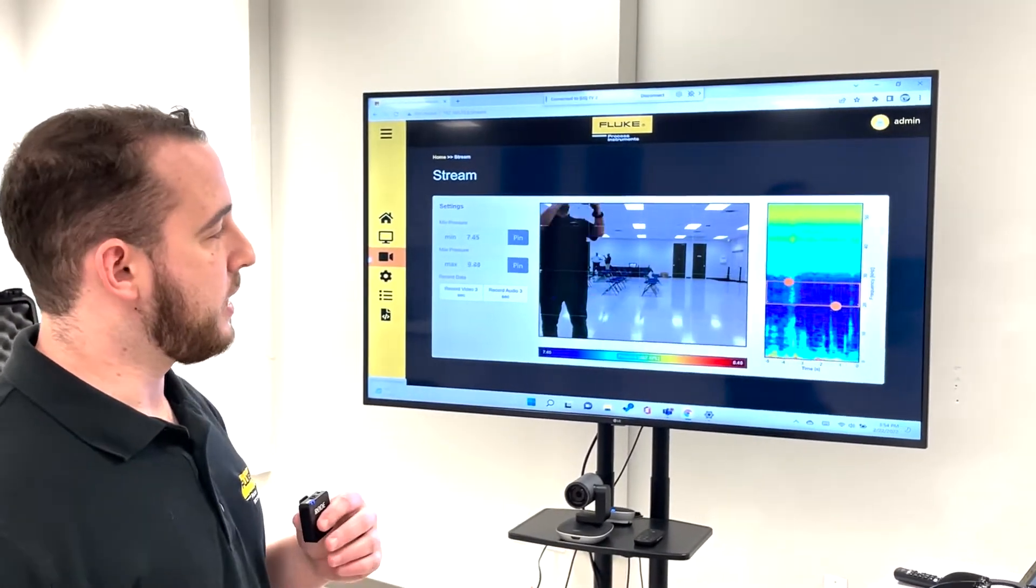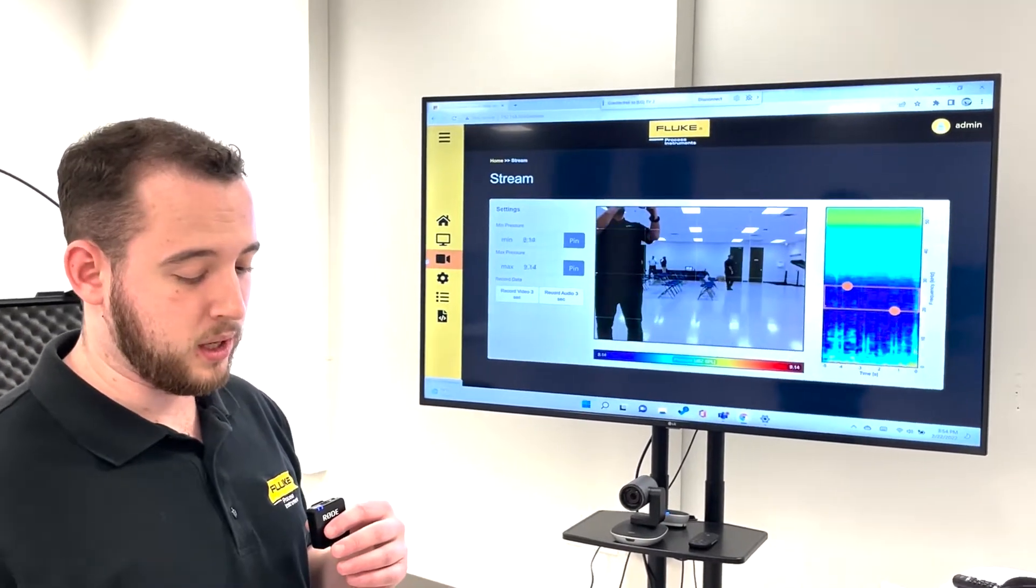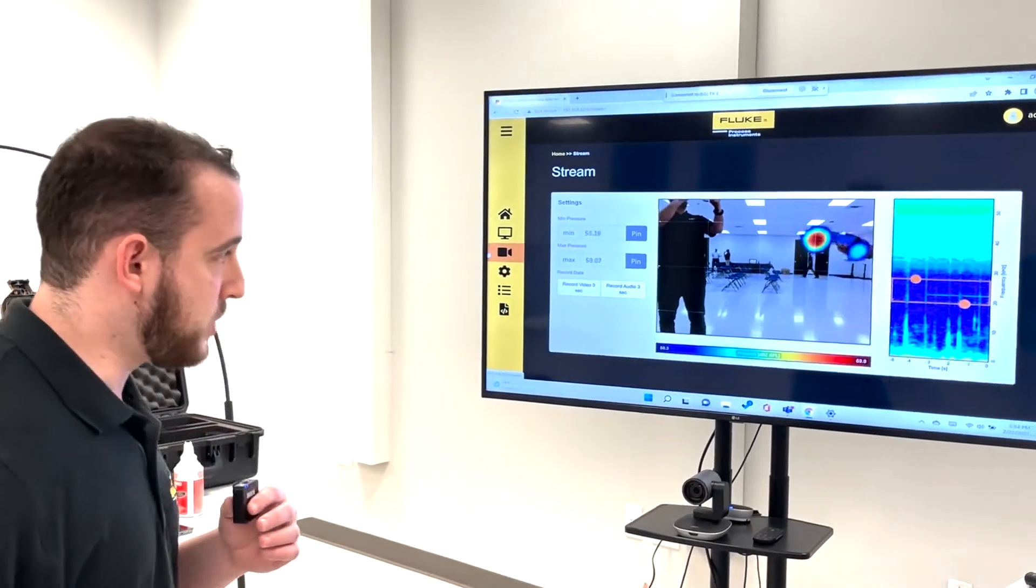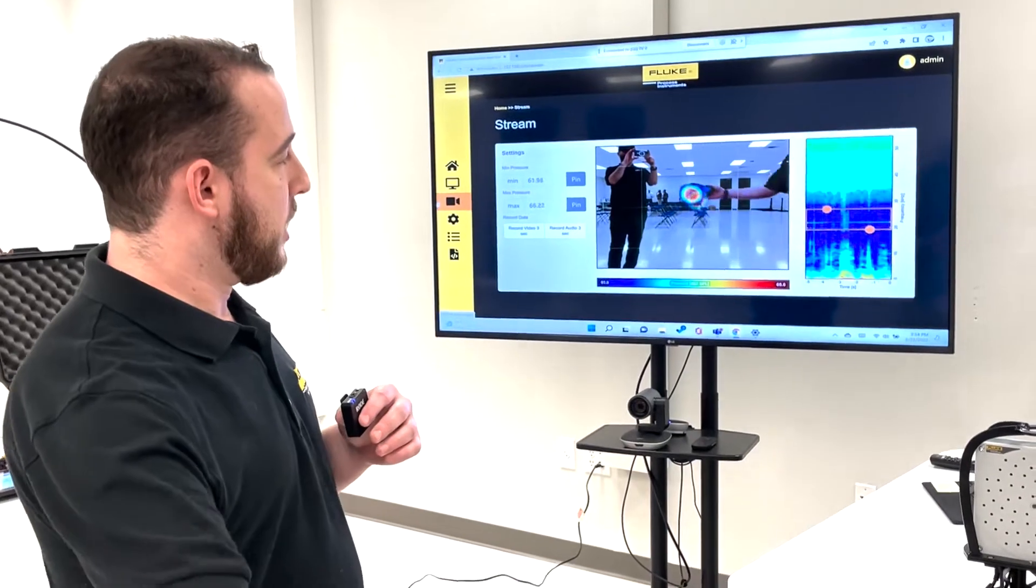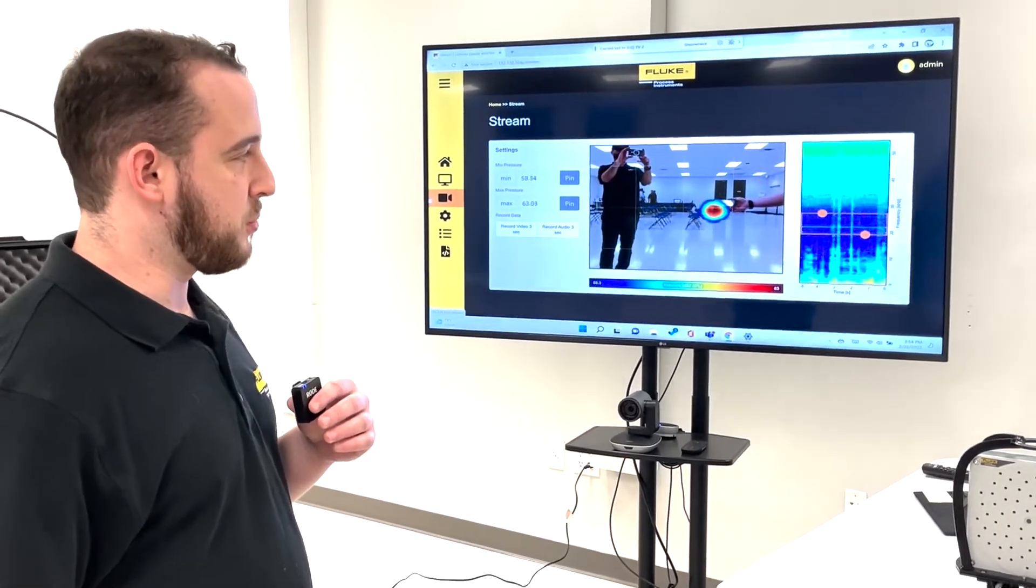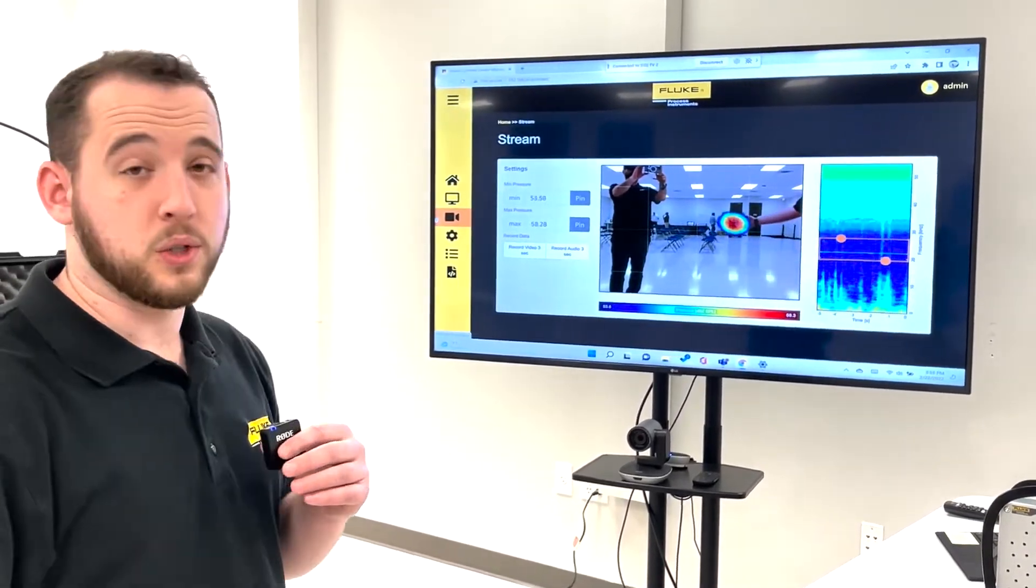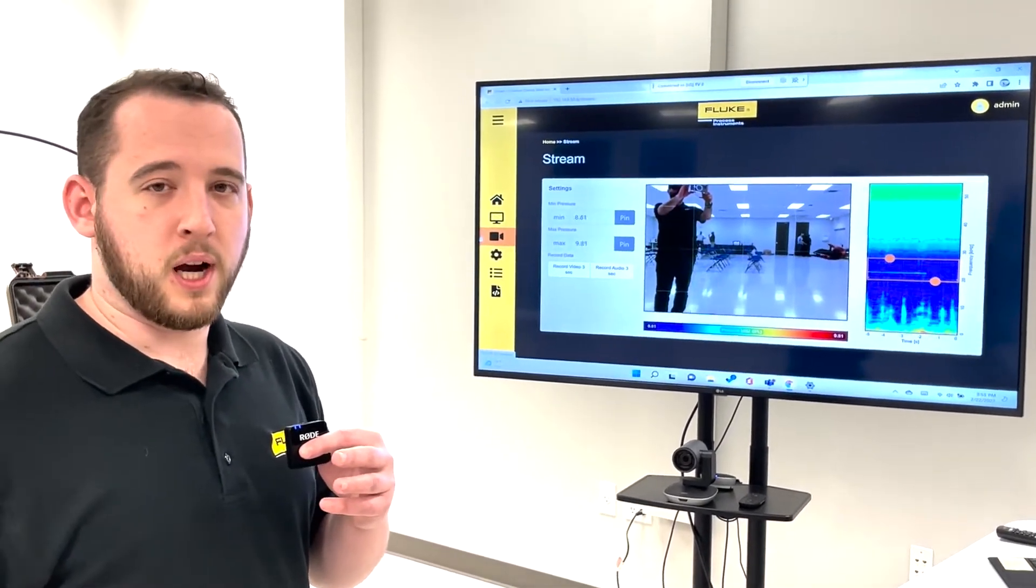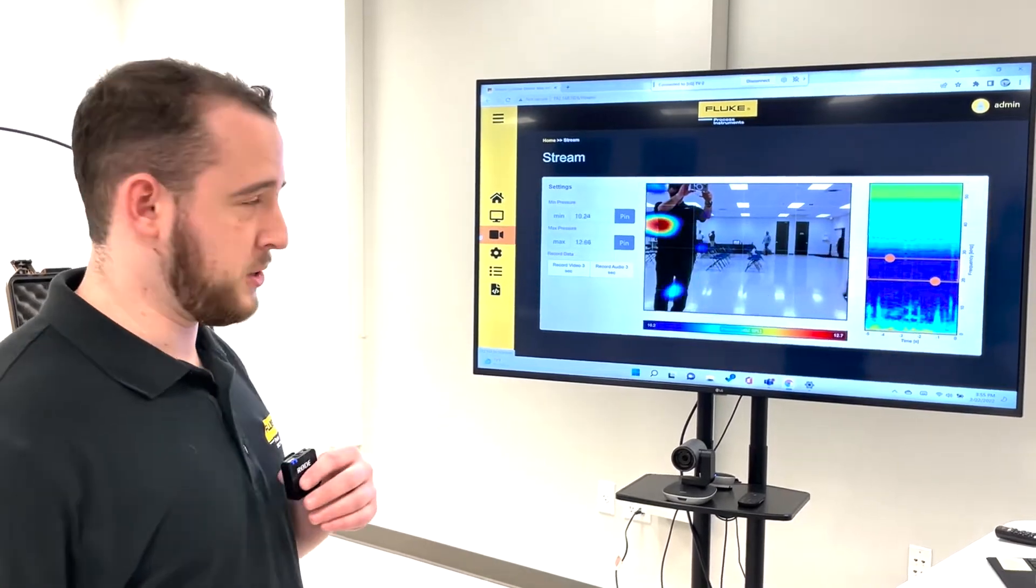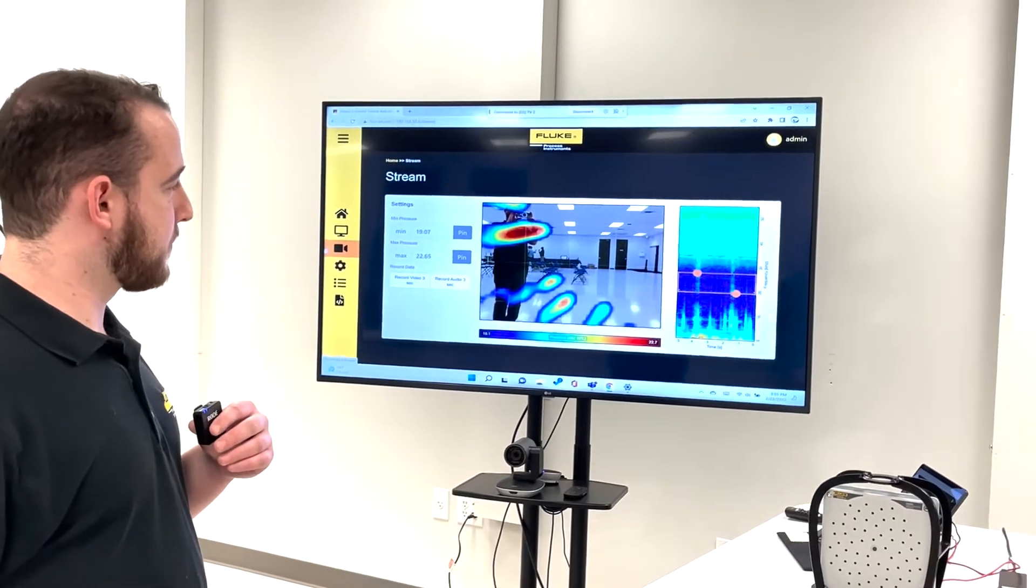JT mentioned one of the leading applications being leak detection and we can kind of simulate that here with the ultrasonic signal coming off of my phone. We've got it at 22 kilohertz and I can't hear it either, but putting this out at full volume on my phone, it's picking it up around 65 decibels and you can see on the spectrogram there on the right, we've got a nice clear signal at that 22 kilohertz. So in a loud, noisy industrial plant environment, you've got a lot of background noise, especially in those lower frequency bands. We're getting some background noise here right now too, so this is actually a great demonstration.